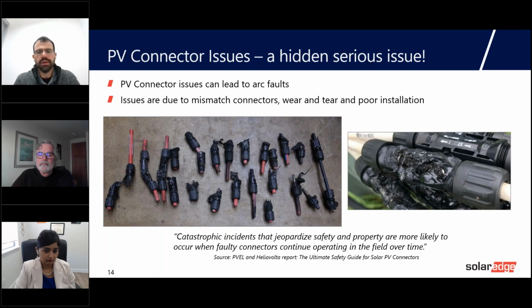This report is available online. It says they inspected several sites and found that about 70% of the sites had issues with connectors, and if not caught early enough, it can lead to what you're seeing here: melted connectors, ground faults, and even fires. If not caught early enough, it can lead to catastrophic failures. The only way up to now to check on that is to go into the field and use a thermal imaging device to check for higher temperatures on the connector.